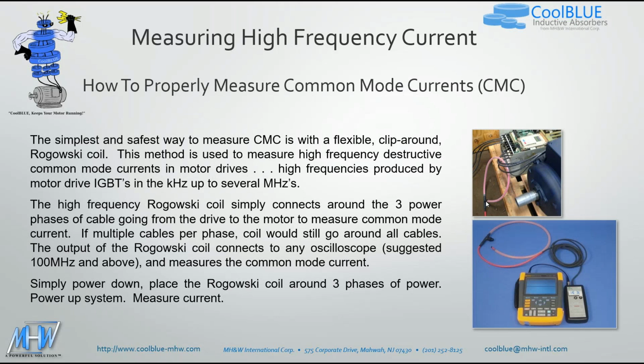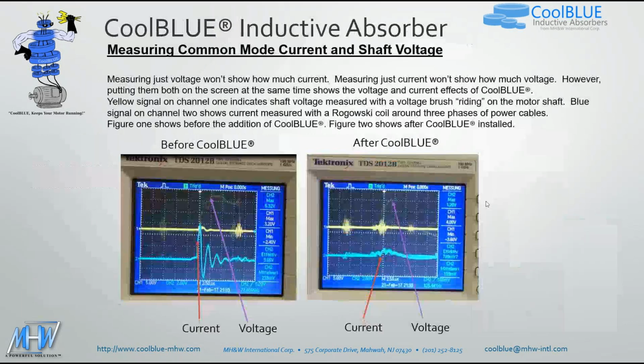The output of the Rogowski coil connects to an oscilloscope, preferably 100 megahertz and above rated, and then you basically measure the common mode current on the oscilloscope. You simply power down, place the Rogowski coil around the 3 phases, power up the system, and measure the current. It's that simple.